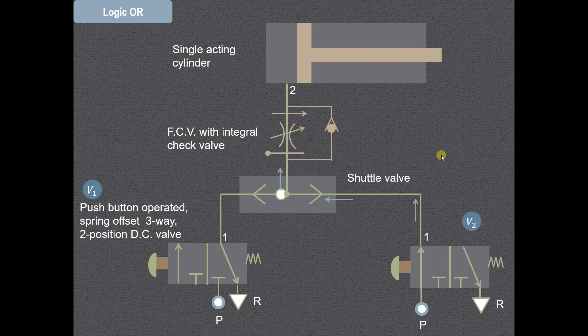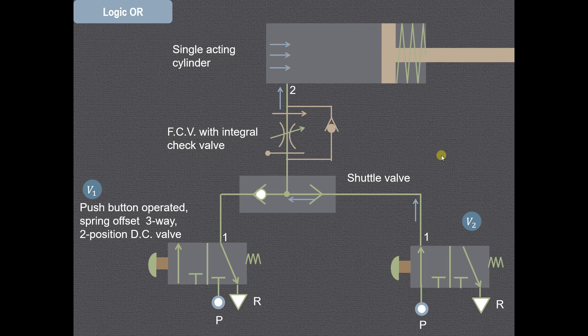As you can see, the air is admitted and there will be compression of the spring while the piston advances. This is the forward stroke obtained in this particular case. Either valve V1 or V2 is operated, and then only we will get this operation. Even though V1 is not operated, there is no problem — we get the operation of the circuit. Operation of either valve V1 or valve V2 is required, and therefore this is known as the logic OR circuit.